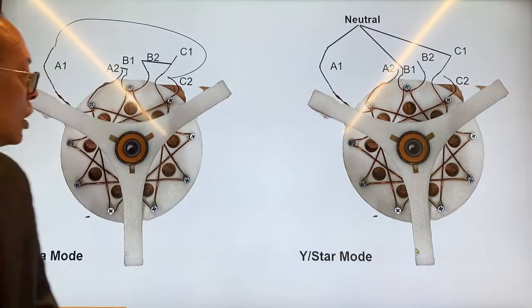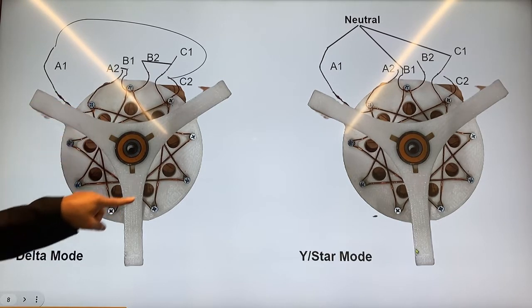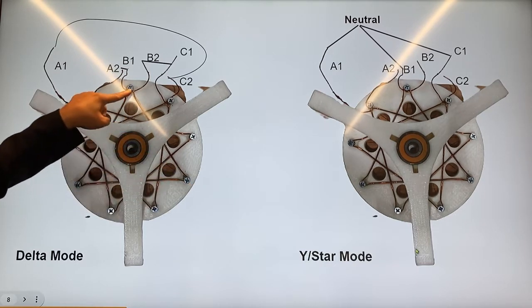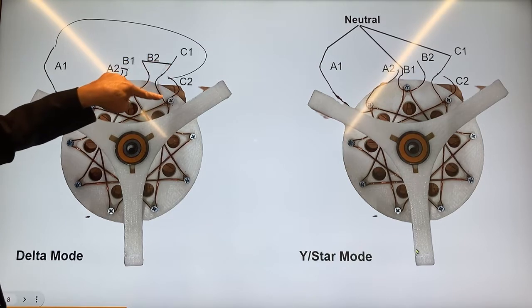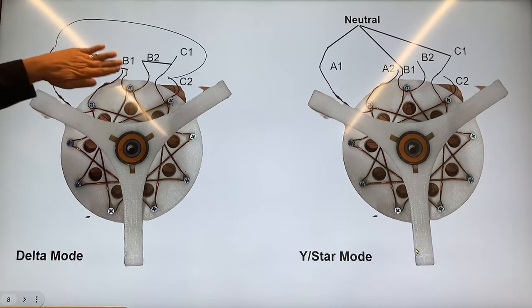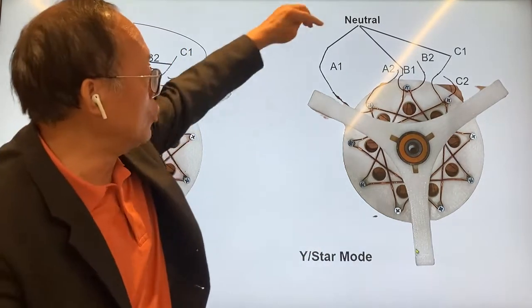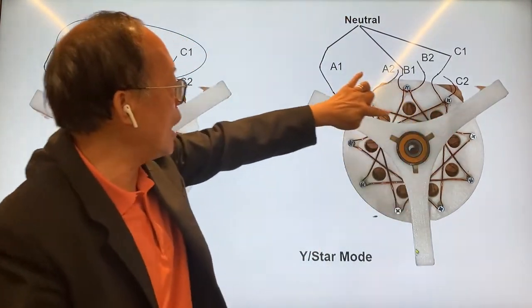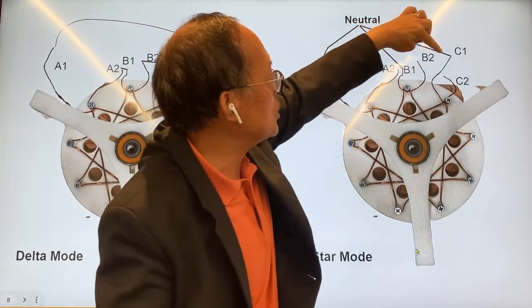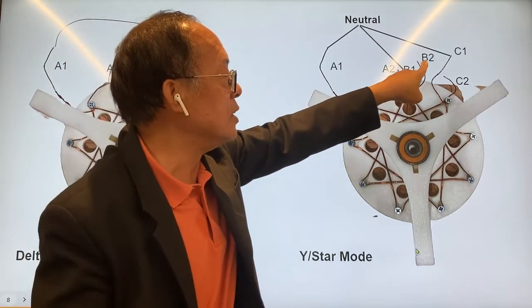This shows how you can connect the Y configuration. In the delta mode: A1 is connected to A2, A2 is connected to B1, B1 connects to B2, B2 connects to C1, C1 goes to C2, and C2 goes back to A1. Phase A is here, phase B is here, and phase C is here. The delta mode is not as efficient in generating voltage as the star mode. In the star mode, A1 goes through here and connects to A2, and A2 would be phase A, because A1, B1, and C1 are all connected to the neutral. So the three-phase power source has phase A, phase B, and phase C.